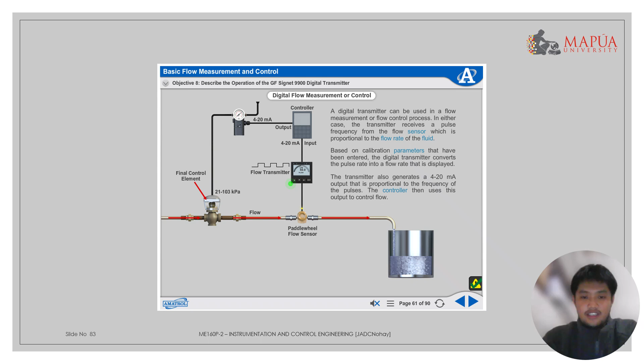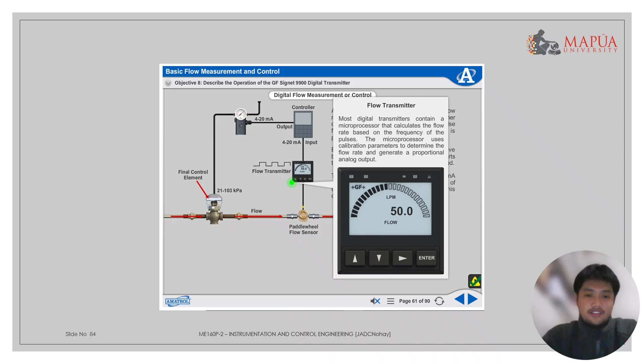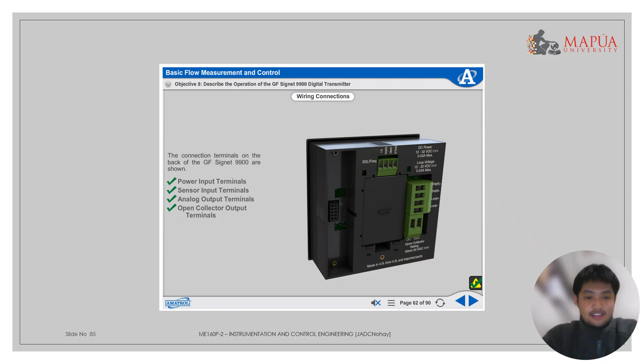Here is the flow transmitter. Most digital transmitters contain a microprocessor that calculates the flow rate based on the frequency of the pulses. The microprocessor uses calibration parameters to determine the flow rate and generate a proportional analog output. Wiring connections. The connection terminals on the back of the GF Signet 9900 are shown.